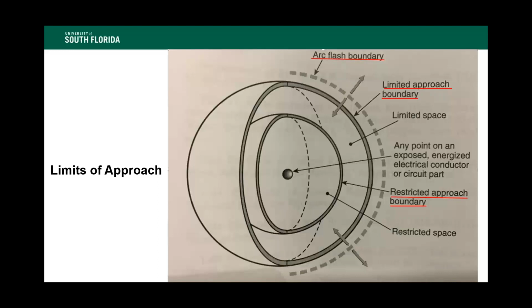We come out to that second sphere with the solid line, and we see that as a limited approach boundary. That's the boundary where we don't want anybody who's not qualified to come closer than. Then that hashed line further out from that second sphere is our arc flash boundary. There's a lot of variation with the location of the arc flash boundary, and there's an actual calculation that can be made based on the voltage and the ampacity, the current of the energized source. That's the one which keeps people from getting burned or having molten metal spewed at them.